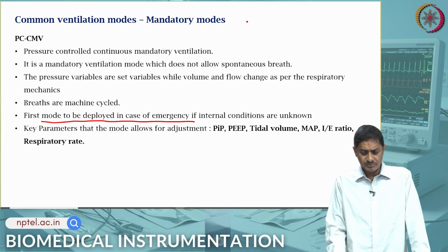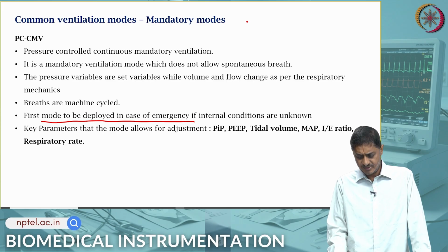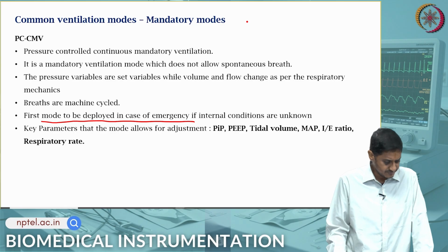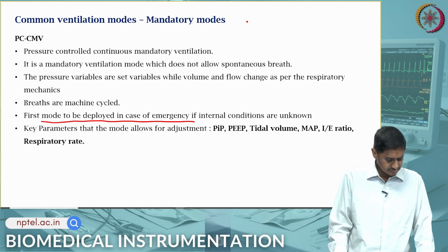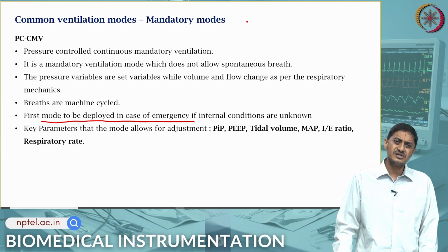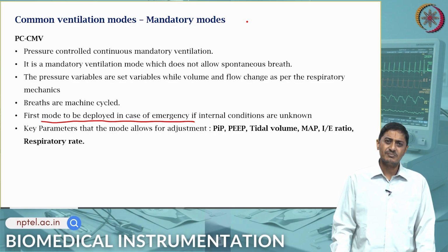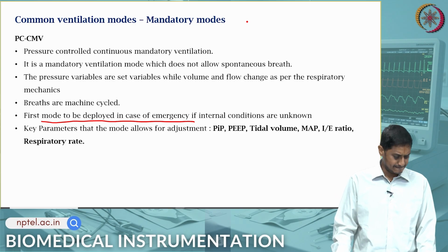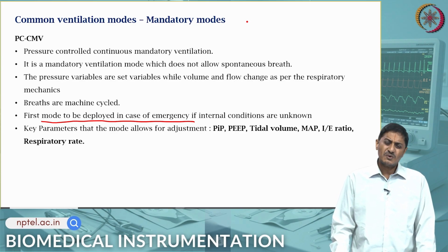This is the mode to be deployed in case of emergency, because we do not know what the internal condition of the patient is. The various things that can be controlled are PIP, PEEP, tidal volume, MAP, IE ratio and respiratory rate. Note that the pressure is only controlled during inspiration, because expiration is a passive process. Is volume controlled?